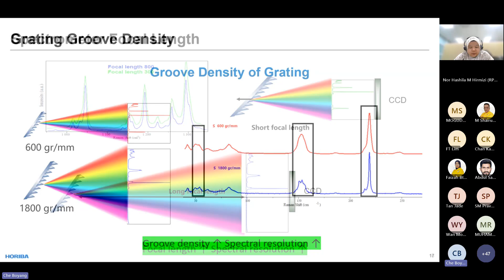The grating will have a lot of fine grooves on one side, and these fine grooves will actually disperse the light. Depending on the number of grooves on the grating, we usually give the density as the parameter. It could be either 600 grooves per millimeter or 1,800 grooves per millimeter. If we use a high groove density, it will disperse the light wider, even though the light is traveling the same distance. So if we use a high groove density, we are able to improve the spectral resolution. High groove density gives you better spectral resolution.